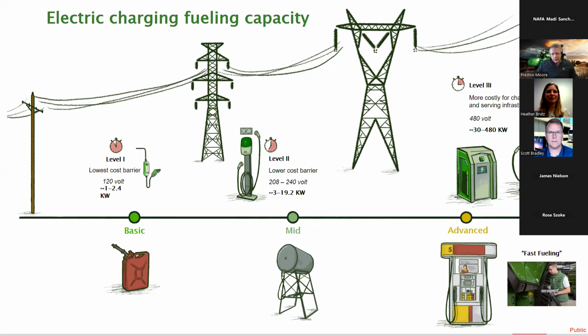As you move out on the fringes of the grid, it gets more and more important to pay attention to what the grid can provide and what you can do. Sometimes the grid upgrade timelines and cost investment are very high and very long. We're seeing lead times anywhere between 20 and 40 months, and as you continue those upgrades, it gets costly pretty quick, because grids don't upgrade proactively, only as the need arises. So a lot of times when you're requesting these, you're looking at the transformer cost and line upgrade costs. That's the area we're looking at to solve for our customers as well.